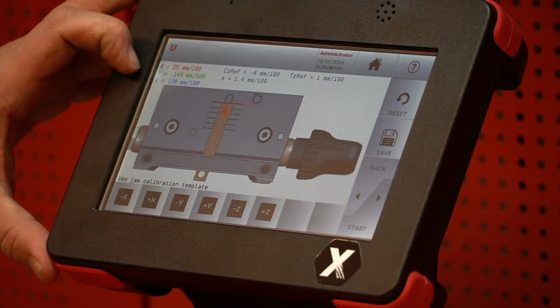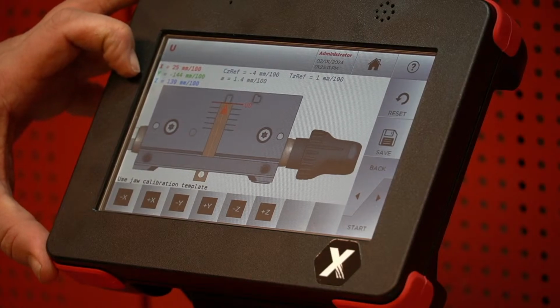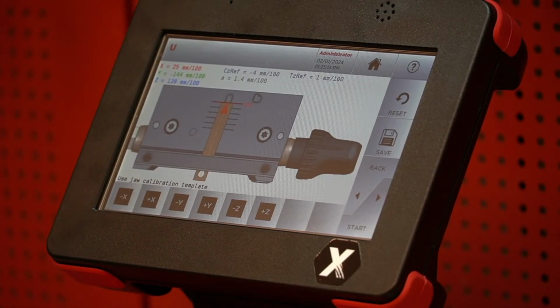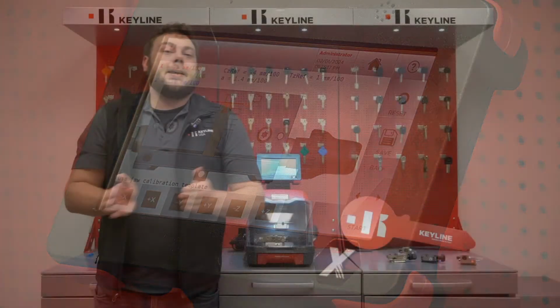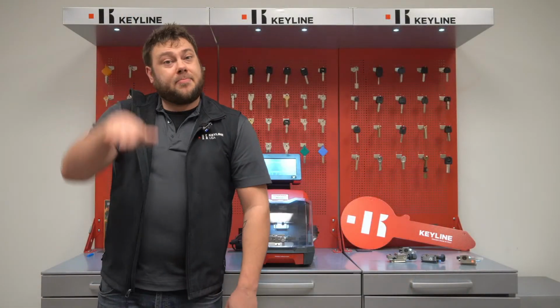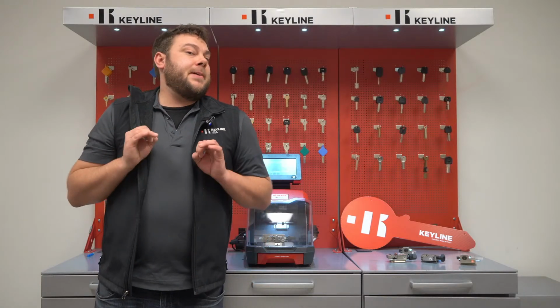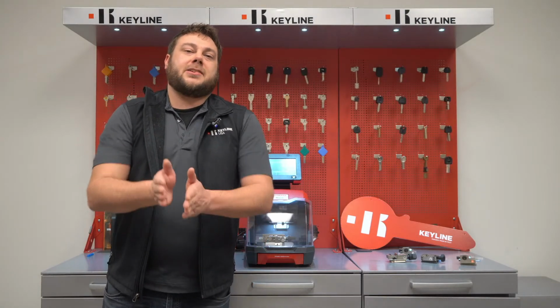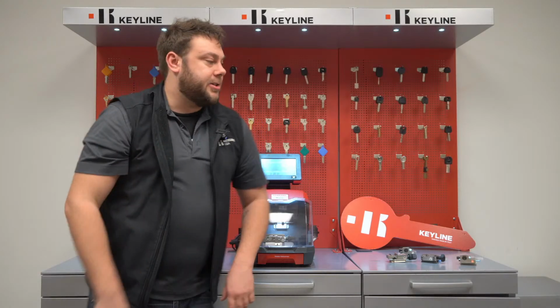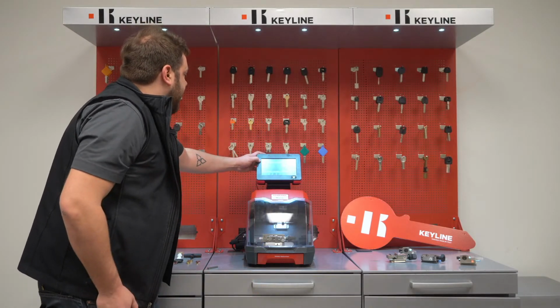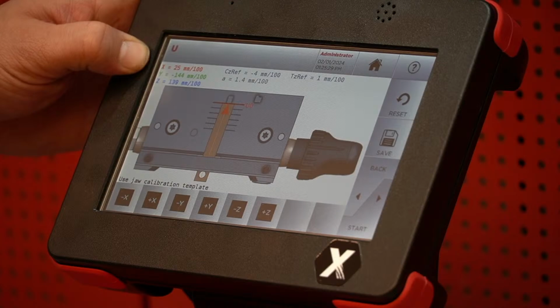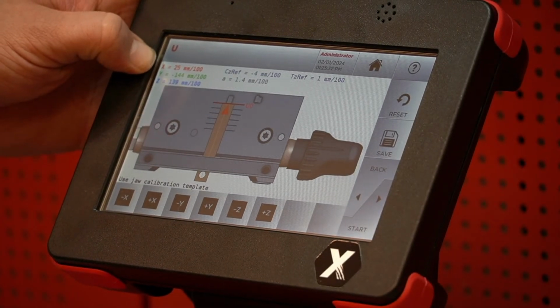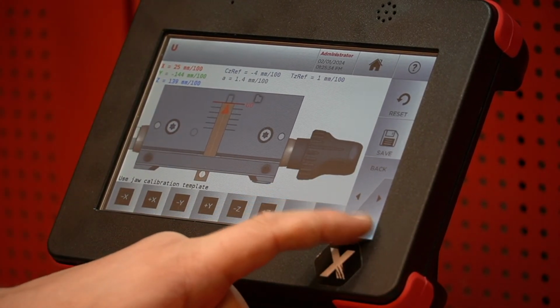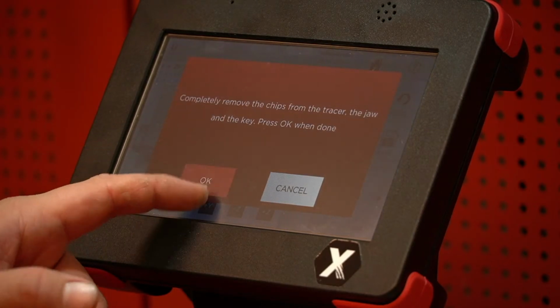Now you'll have X, Y, and Z values up in the top left corner. X is forward, backward movement. Y is left, right movement. And Z is up, down movement. So if you usually have big jumps, you can tell which direction you're getting the differential calibration. So you make note of the values, 25, negative 144, and 139. I like to write them down. But then all you do is you hit start, and then OK.